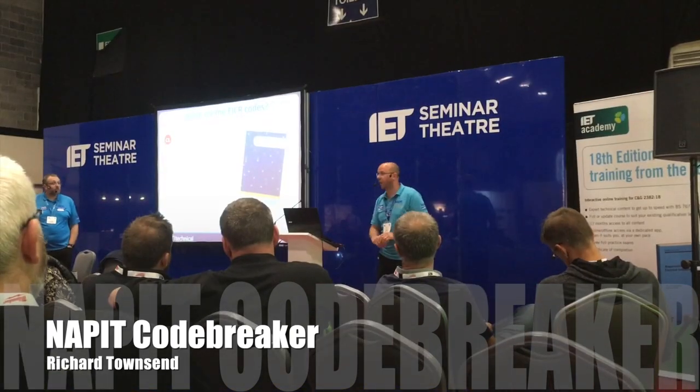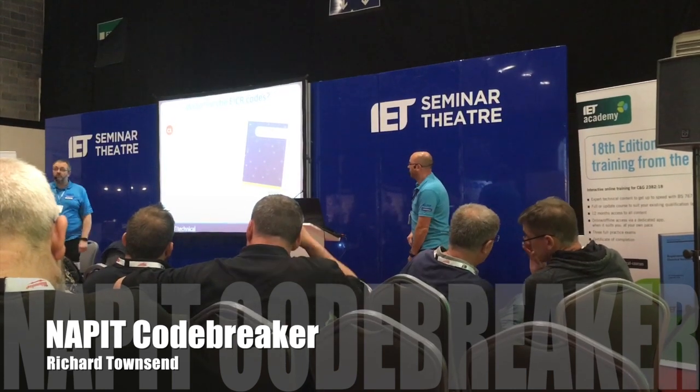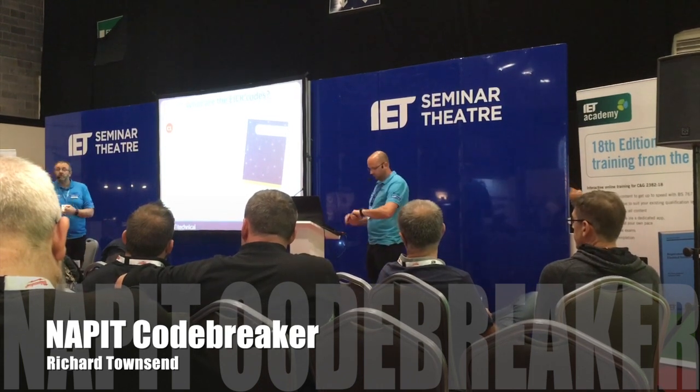Reminder of what the codes are. What's a C1 mean? The danger's present. There's risk of injury. I can see it, I can touch it, it can kill me now. You've got direct access to live parts, so we would give that a C1.